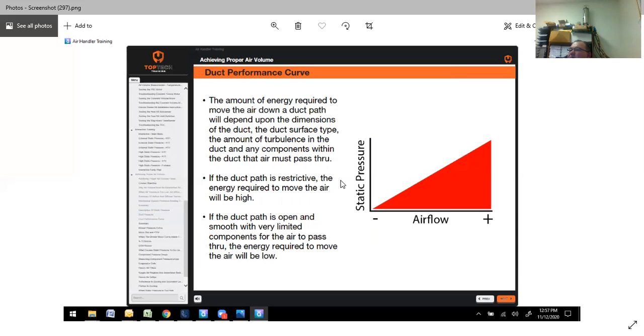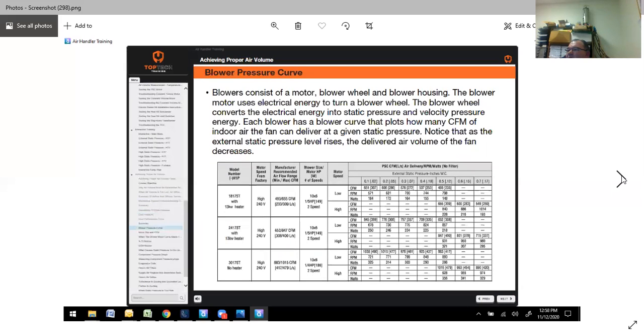The amount of energy required to move air through a duct path will depend on the dimensions, duct surface, and turbulence. If the duct path is too restrictive, the energy required to move the air will be high, which is going to increase power consumption. Along with power consumption comes noise. Also there will be comfort issues. If the duct path is open and smooth with very limited components for the air to pass through, the energy required to move that air will be low. That's what you're selling when you sell variable speed: comfort, noise, kind of a smooth, easy comfort. So if your duct is restricted, it's going to cause you all kinds of issues and increased power consumption.